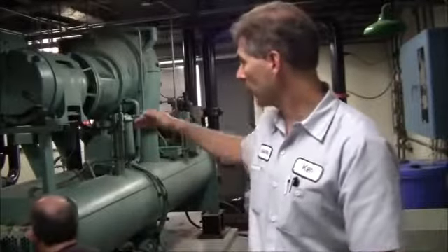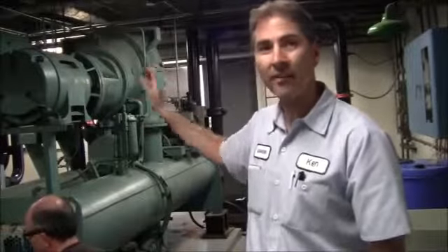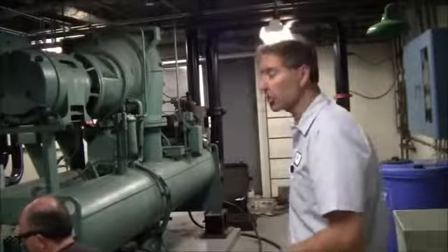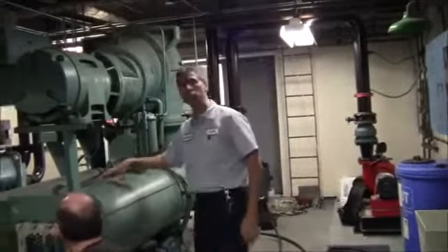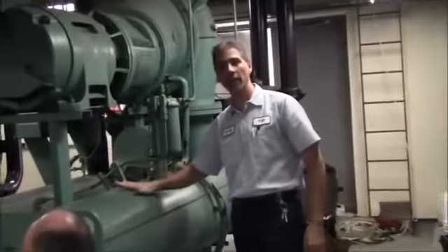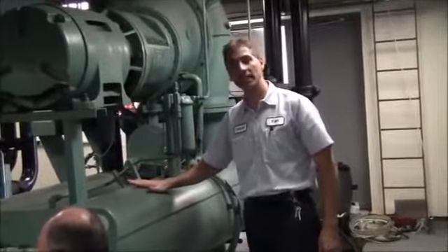Today's training, what we're doing is we are eddy current testing the tubes that are in this chiller right behind me. There's a condensing section and an evaporator section. So let me go over the chiller itself. It's a shell and tube chiller. This here that I've got my hand on, this is the condenser.